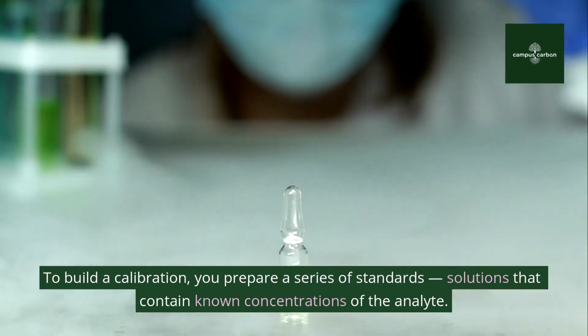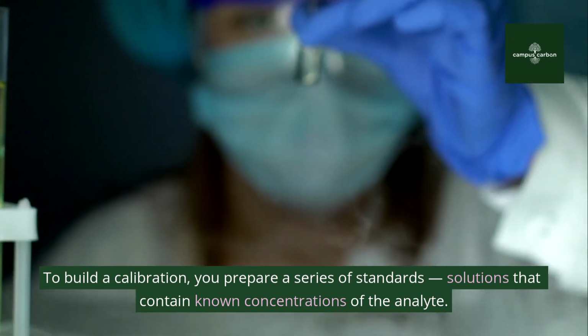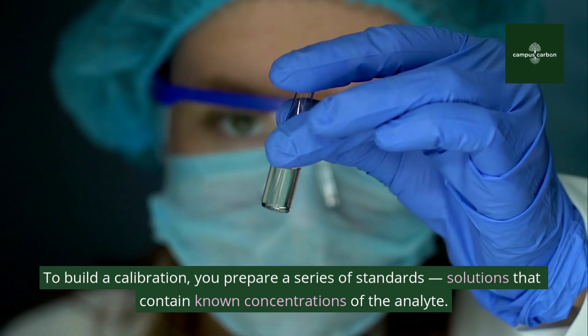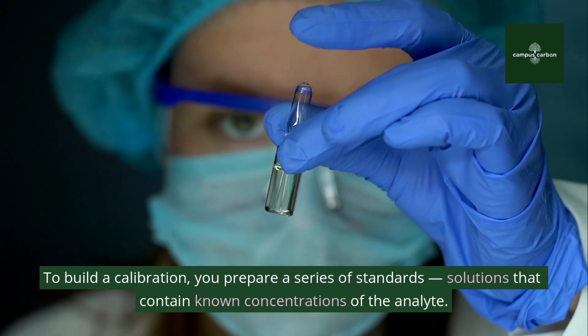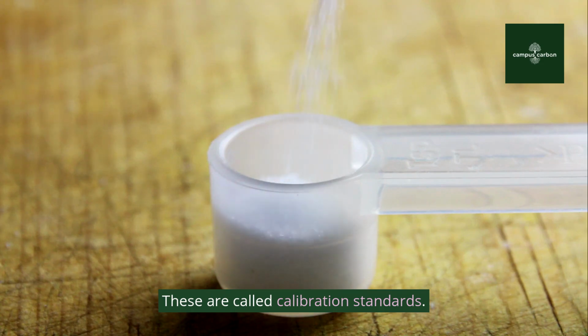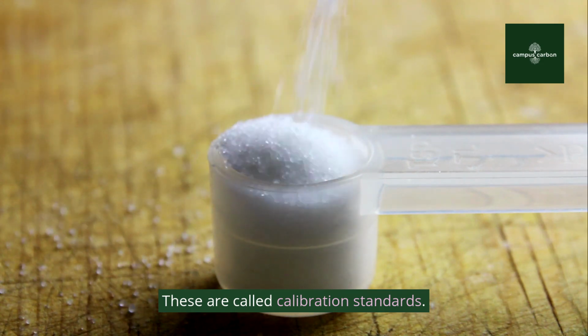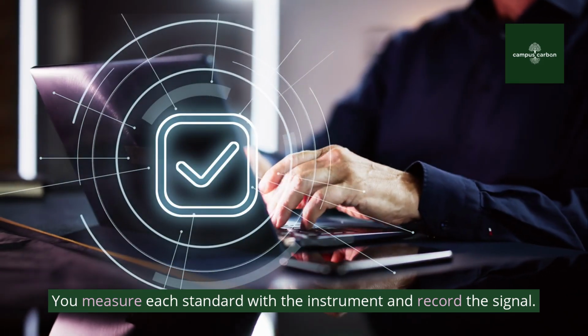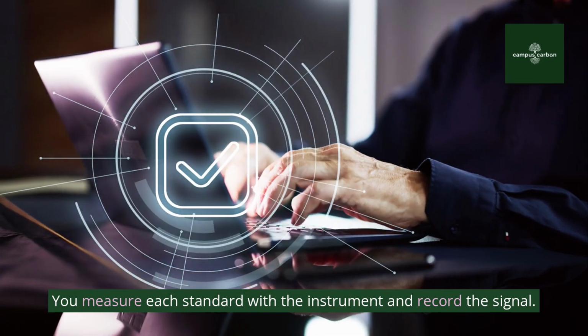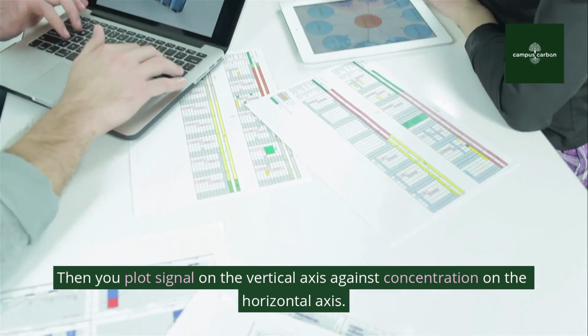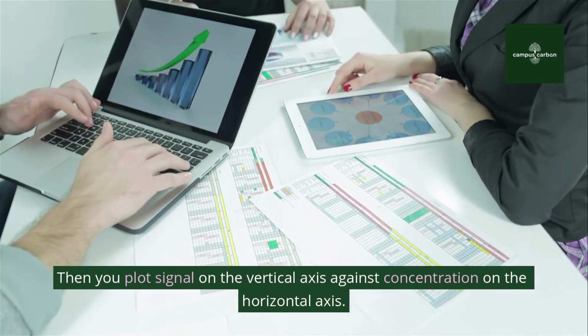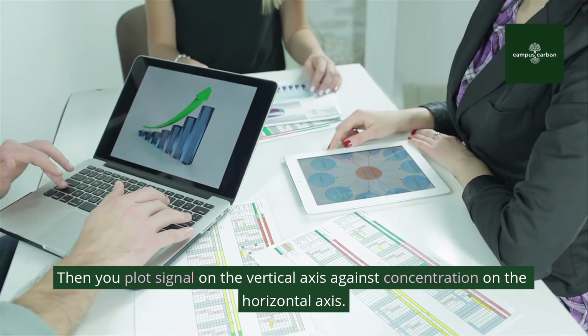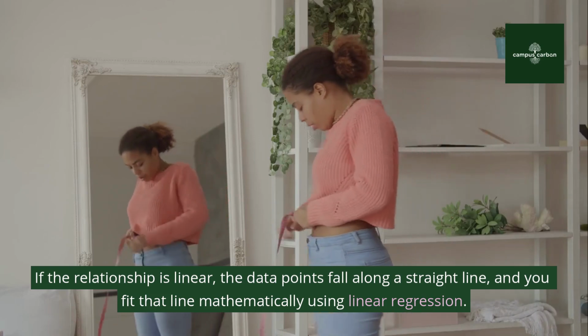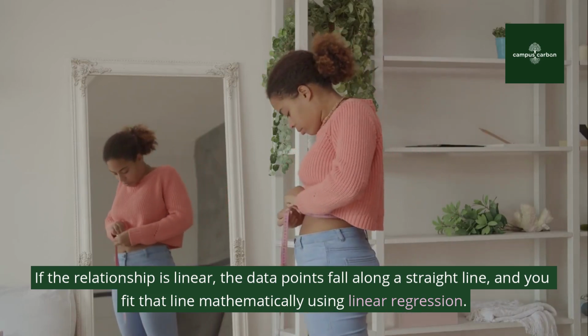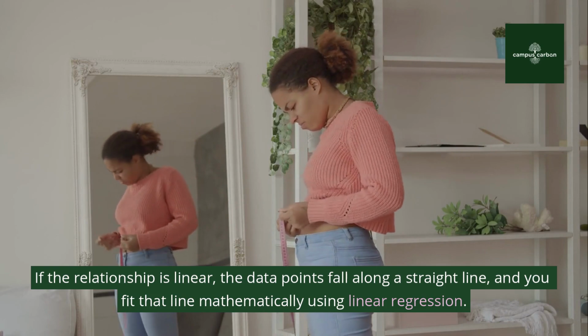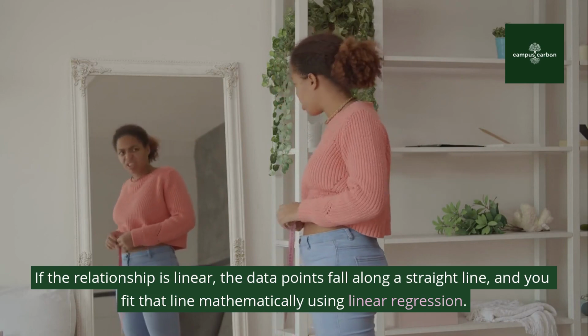To build a calibration, you prepare a series of standards, solutions that contain known concentrations of the analyte. These are called calibration standards. You measure each standard with the instrument and record the signal. Then you plot signal on the vertical axis against concentration on the horizontal axis. If the relationship is linear, the data points fall along a straight line, and you fit that line mathematically using linear regression.